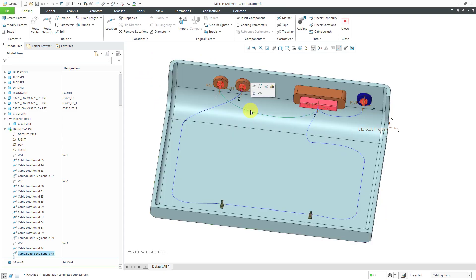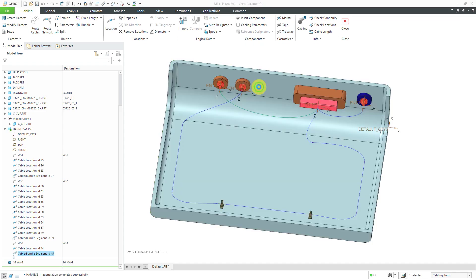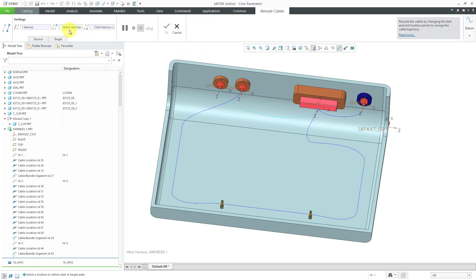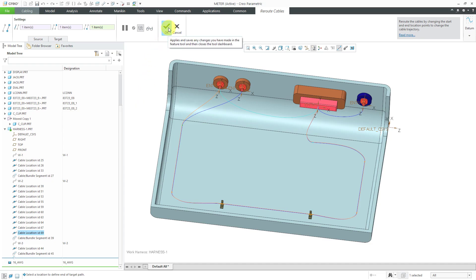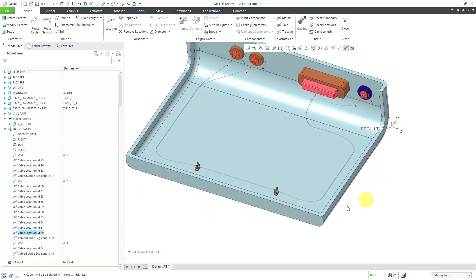For this other particular wire, since I've already defined a bunch of different location points in the previous wire, in the mini toolbar we have the Reroute command. With Reroute, we can follow the routing of other wires. I can say let's start at this location and pick the end location — now we have both wires going along the same routing. I can hit the check mark, change over to a thick cable display, and there you see the harness with the three individual wire conductors.